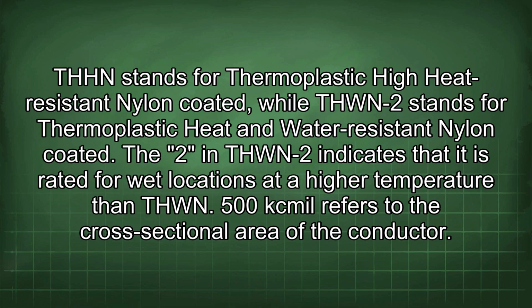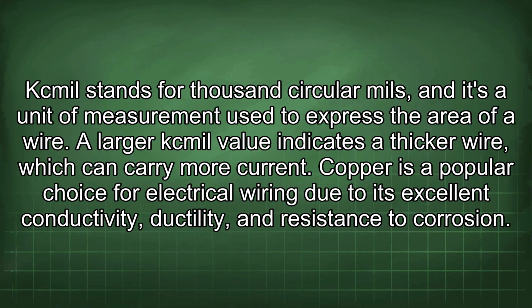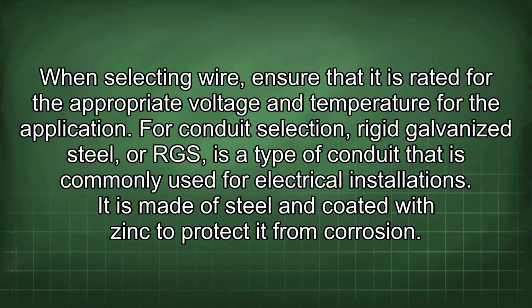500 kcmil refers to the cross-sectional area of the conductor. Kcmil stands for 1000 circular mils, and it's a unit of measurement used to express the area of a wire. A larger kcmil value indicates a thicker wire, which can carry more current. Copper is a popular choice for electrical wiring due to its excellent conductivity, ductility, and resistance to corrosion. When selecting wire, ensure that it is rated for the appropriate voltage and temperature for the application.